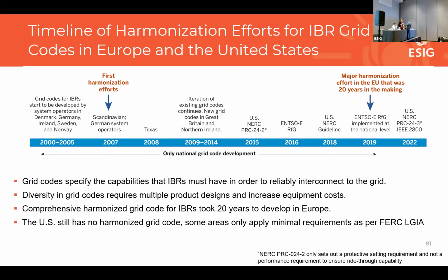So now in the entire Europe, there is a unified harmonized standard for interconnection of inverter-based resources, and they actually have it also beyond the transmission level, and that relates even to smaller inverter-based resources. So that took 20 years to get this harmonized effort done in Europe, but here in the US we still don't have a harmonized interconnection standard. It still differs region to region. In some regions it's as basic as the pro forma LGIA. In some regions there are more stringent interconnection requirements, but we need harmonized interconnection requirements across the US because, whether it's one power system or 3 power systems, the performance of IBRs is equally important to all of these regions.